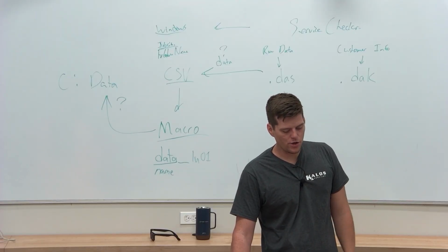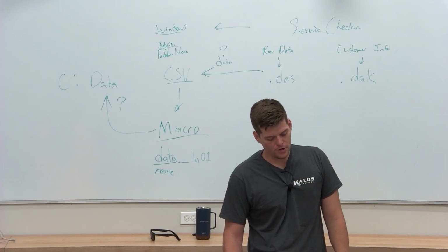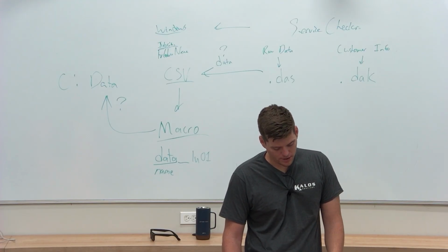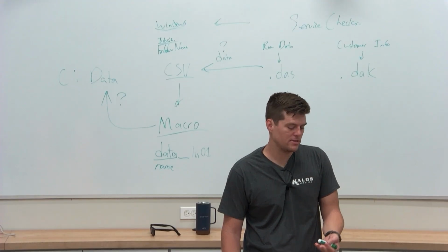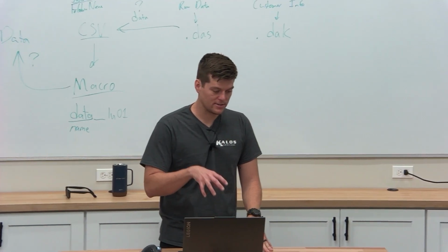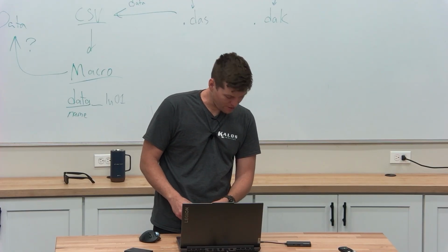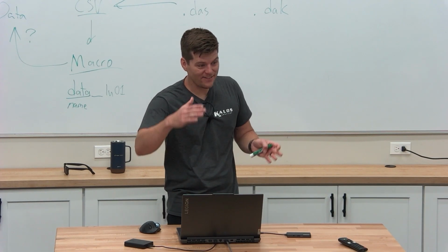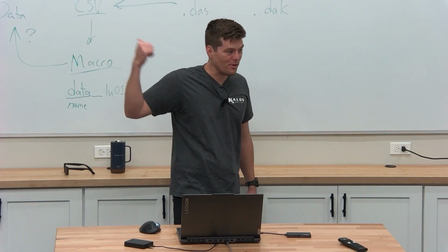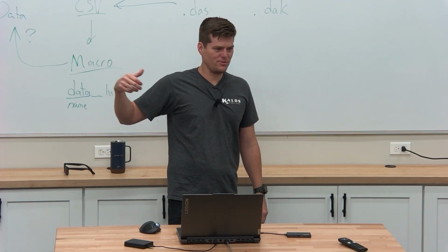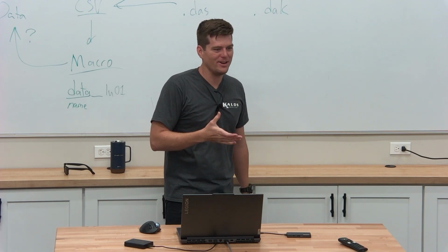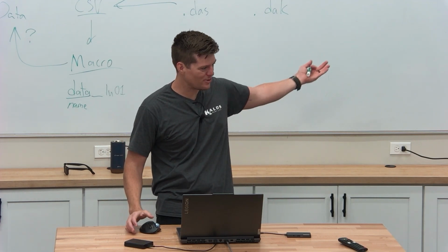Otherwise, you can go in and copy and paste, and it'll say, hey, do you want to replace duplicates? And you can say yes, but the problem is if the data you're transferring only has 10 indoor units, and the data that's already in there has 32, then it's going to leave any remainders after that. And then when you go to pull the macro, you're going to have a bunch of indoor units doing some crazy stuff that have nothing to do with your unit. How is this unit in cooling when my outdoor unit's in heating?